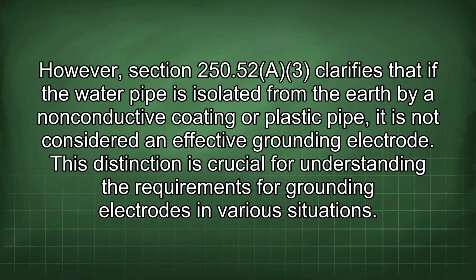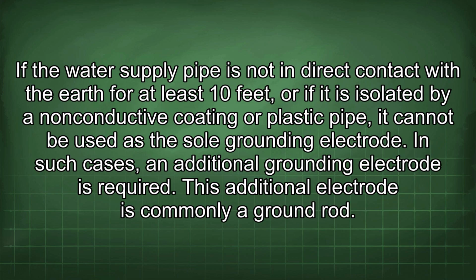However, Section 250.52(A)(3) clarifies that if the water pipe is isolated from the earth by a non-conductive coating or plastic pipe, it is not considered an effective grounding electrode. This distinction is crucial for understanding the requirements for grounding electrodes in various situations. If the water supply pipe is not in direct contact with the earth for at least 10 feet, or if it is isolated by a non-conductive coating or plastic pipe, it cannot be used as the sole grounding electrode. In such cases, an additional grounding electrode is required.